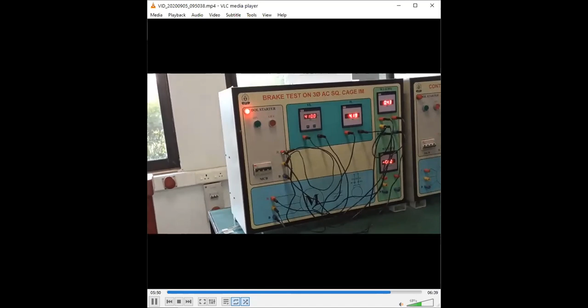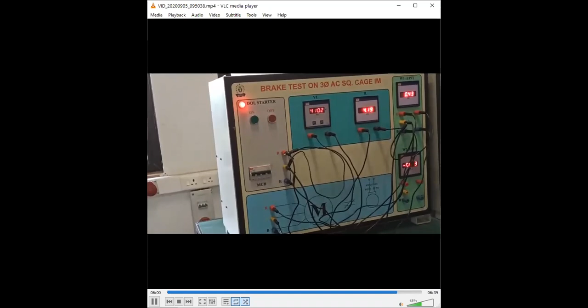Now your machine is drawing the current. Let me just show you those reading. Now please note down, this is a no load condition. So your no load voltage you should note down 410. Your no load current is around 4.1 ampere and power is around 0.43 kilowatt. Second, you should note down, we have not applied any load to the motor, and you should observe that zero load is applied to the motor.